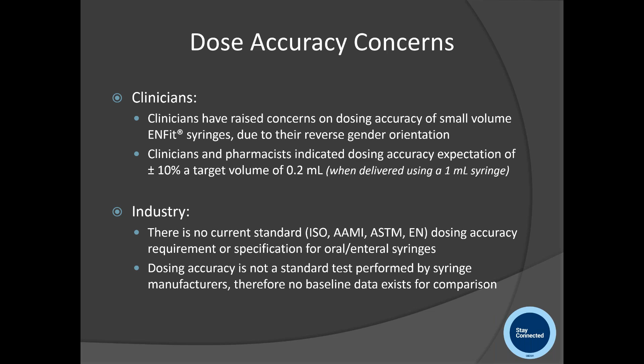But unfortunately, there were not standards in place, neither ISO, AAMI, or any other type of standard that specified or required a certain amount of dose accuracy for oral or enteral syringes. And there's a big reason for that. One is that with oral syringes today, there's no standard for the dimensions of an oral tip syringe. And also, of course, an oral syringe normally will be administered orally into someone's mouth, and obviously there's no standard for a mouth as well. So there's no standard in place, and dosing accuracy is not a test performed by syringe manufacturers. So there really wasn't a baseline. So this was a challenge for the industry to look more closely at.